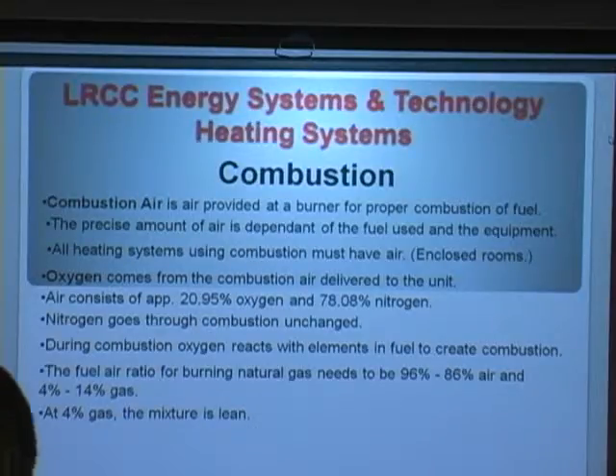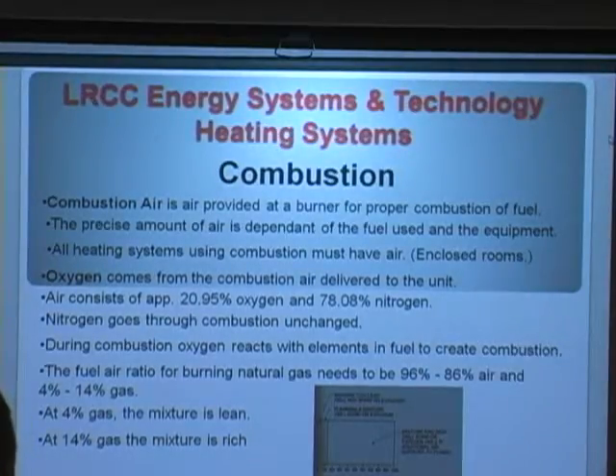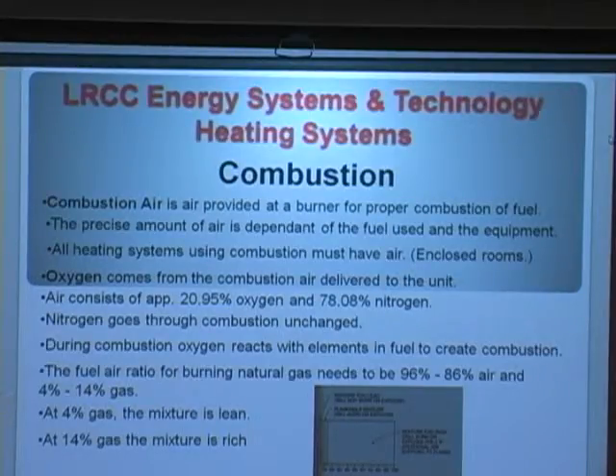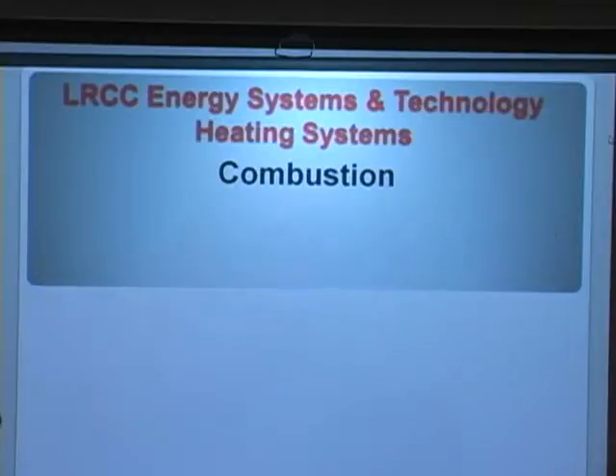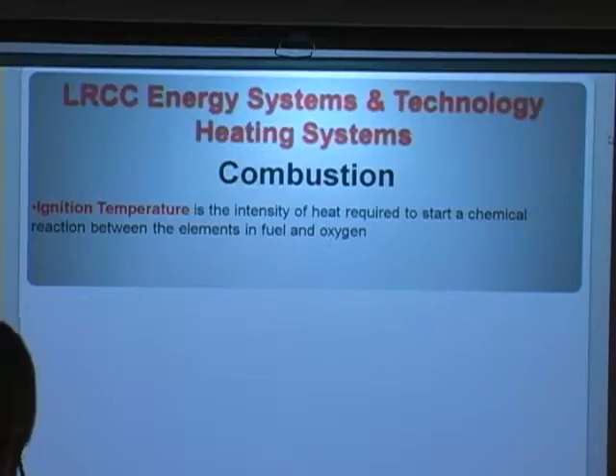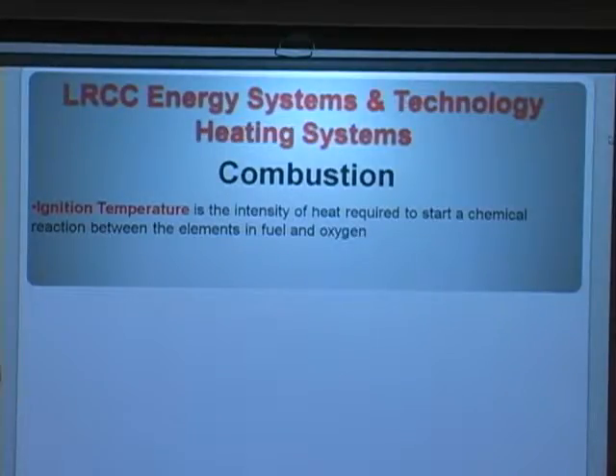A lean fire means we have very little gas and more oxygen. At 14%, we consider that a rich flame. If you're running a burner that's running rich at 14%, its efficiency is probably down because it's utilizing more gas — and that's what you're paying for. The gas is what costs money; oxygen is free. The ignition temperature is the intensity of heat needed to start the chemical reaction between the fuel and the oxygen.